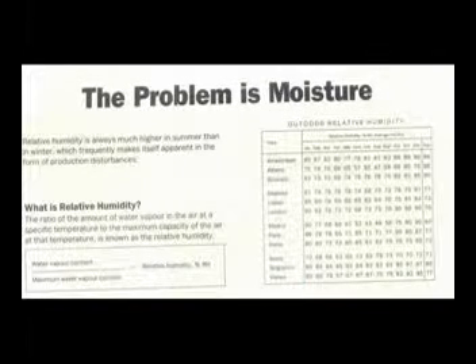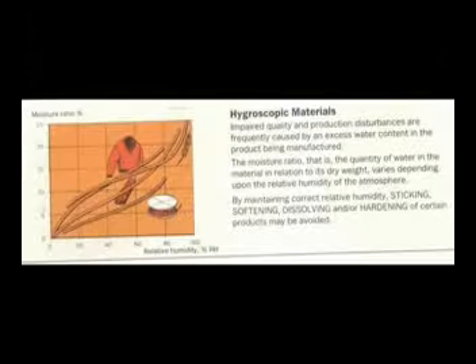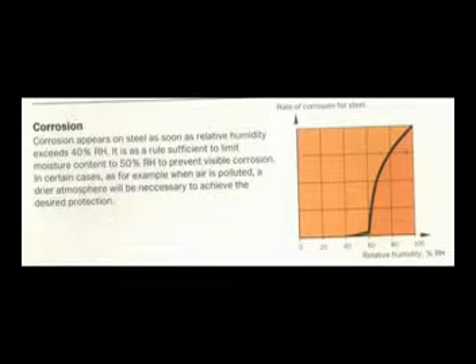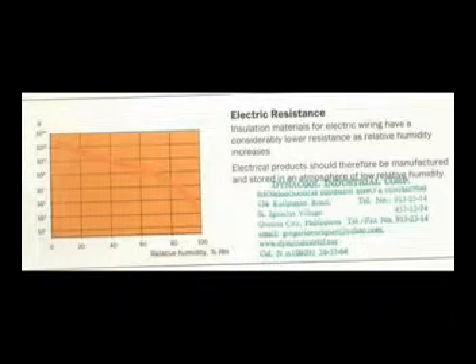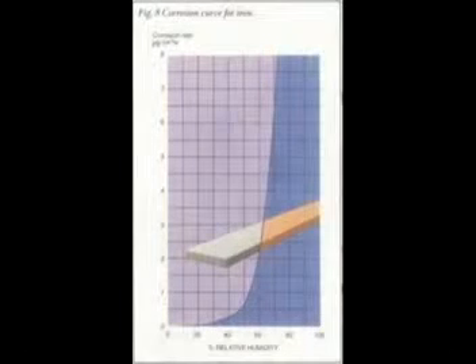In the pictures that you have seen, there are parts that corrode, electronic PC boards that build up oxidation, molds, and in copper and gold, the green corrosion. These are all caused by water or moisture. To prevent it, there must be a good dehumidification system, as we are promoting and carrying. In the picture, the problem is moisture. There are three graphs. One is the corrosion graph. As you can see, when the moisture or humidity in the room is high, the rate of corrosion increases at an exponential rate.